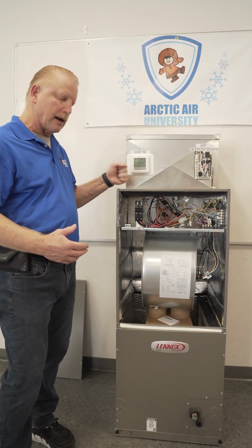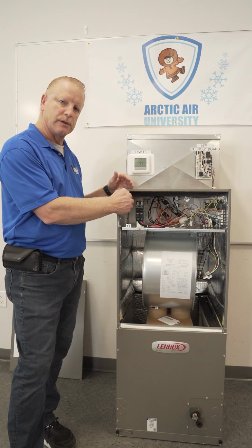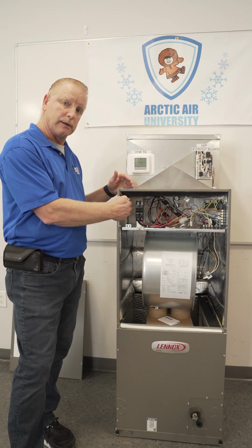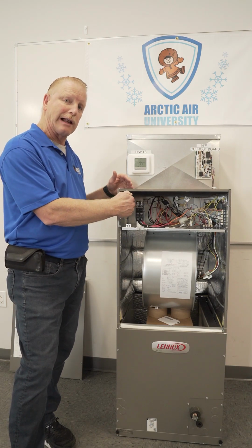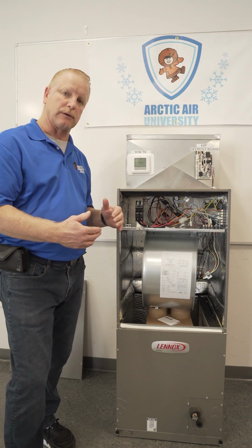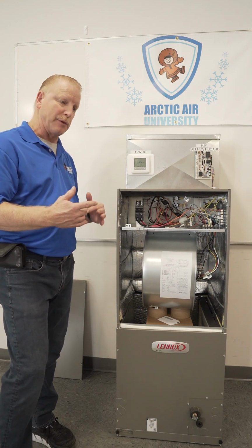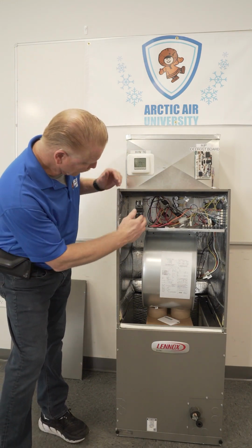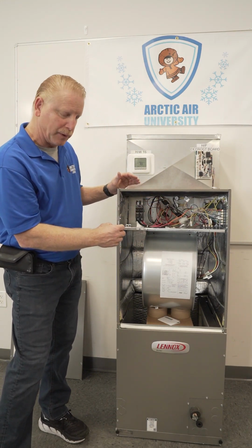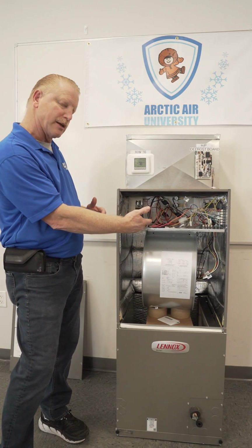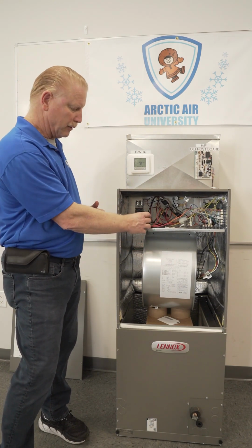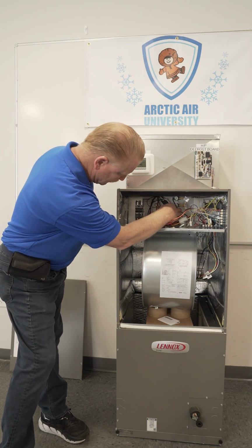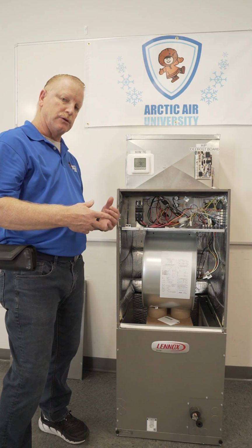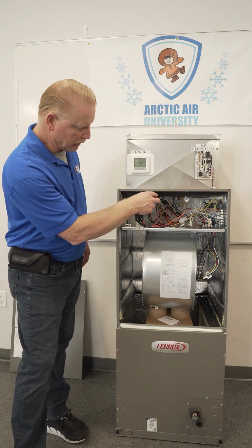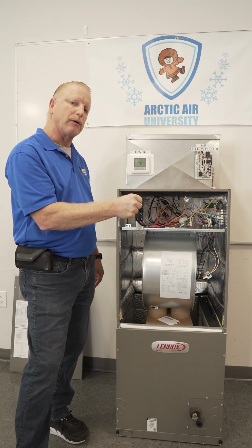Before you take this air handler into a crawl space, into an attic, install your strip heaters outside by the truck, all right? You're gonna make yourself a lot harder job if you try to do this in a crawl space, all right? That's tip number one for the day. To install these strip heaters, the circuit breaker for this particular unit comes with it. You want to let that hang. Behind here, there's a plate that you're going to have to cut out. You can use your sheet metal snips to cut the knockouts out and then remove that whole plate.